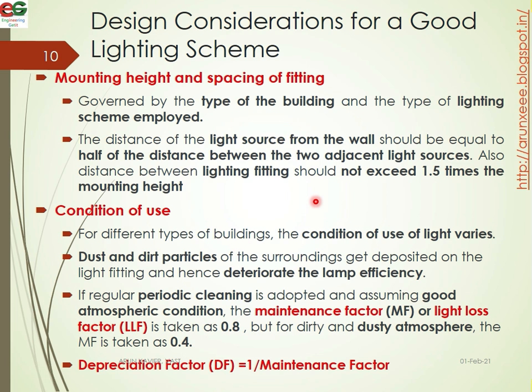Next is the condition of use for different types of buildings. Dust particles and other particles from the surroundings are deposited on the light fittings, hence deteriorating the lamp efficiency. If regular periodic cleaning is adopted and good atmospheric conditions are assumed, the maintenance factor or Light Loss Factor (LLF or MF) should be considered as 0.8. In a dirty or dusty atmosphere, we consider 0.4.